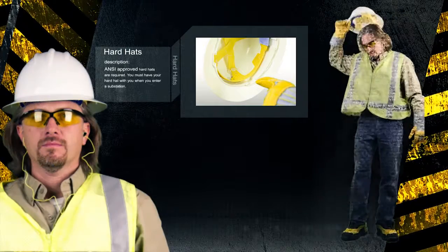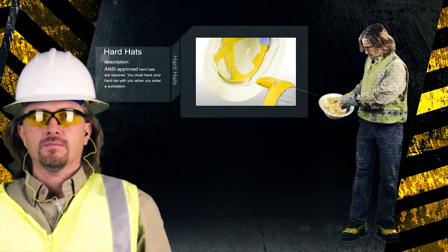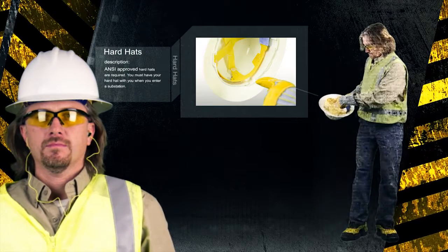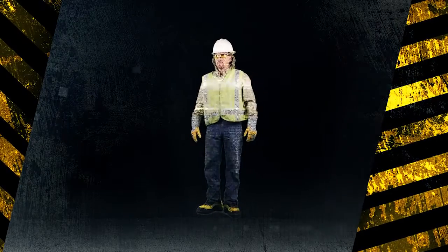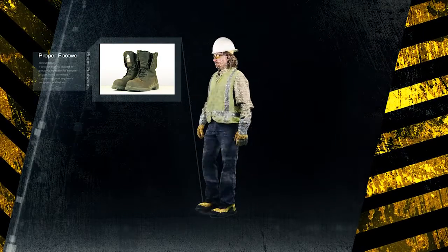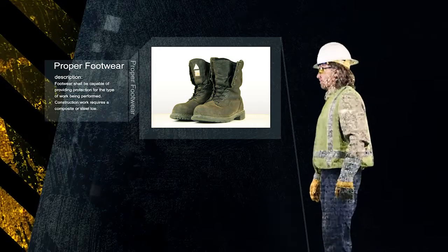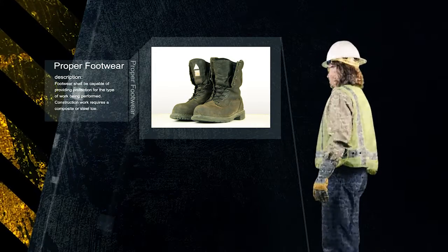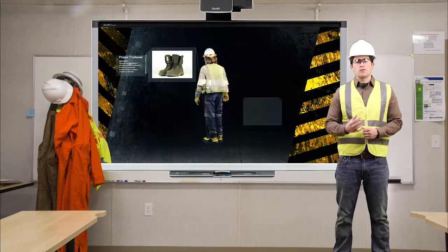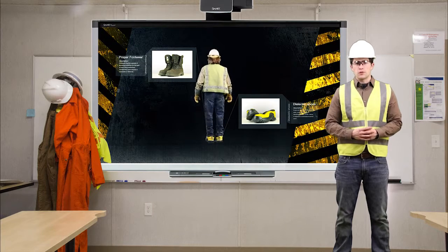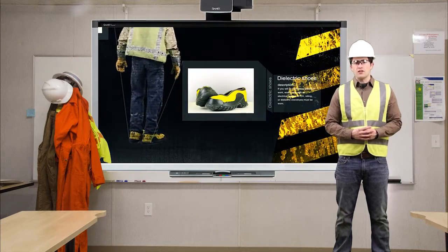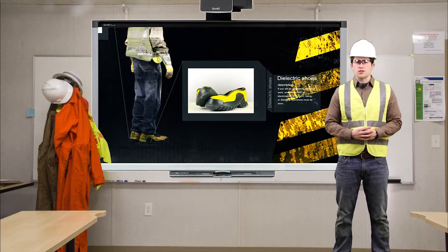For head protection, ANSI-approved hard hats are required. Only attachments designed for use on hard hats shall be used. You must have your hard hat with you when you enter a substation. Footwear shall be capable of providing protection for the type of work being performed. For example, construction work requires a composite or steel toe. If you will be performing electrical work, boots with an electrical hazard or EH rating, or dielectric shoes, must be worn.